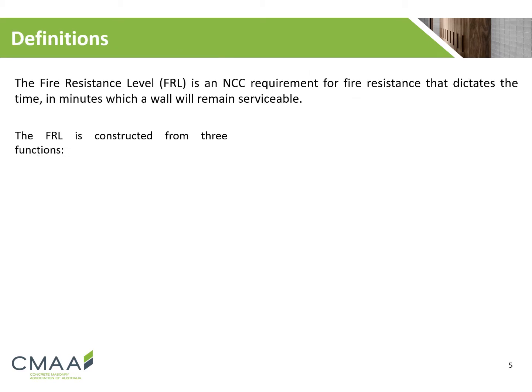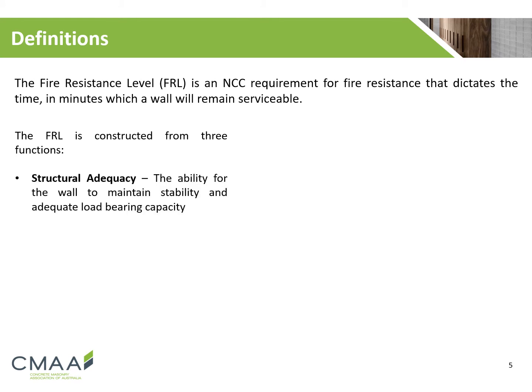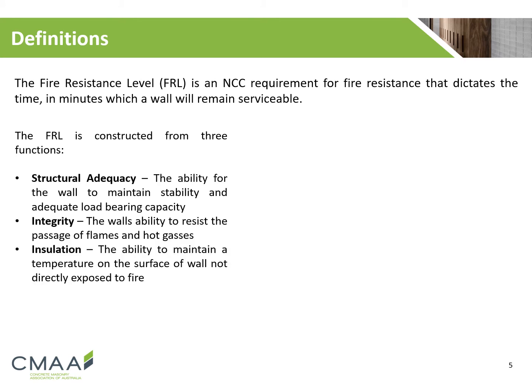The FRL is an NCC requirement for fire resistance that dictates the time in minutes which a wall will remain serviceable when exposed to fire. The FRL is constructed from three functions: structural adequacy, integrity and insulation. Structural adequacy is the ability for the wall to maintain stability and adequate load bearing capacity. Integrity is the wall's ability to resist the passage of flames and hot gases. Insulation is the ability to maintain a temperature on the surface of the wall not directly exposed to fire.